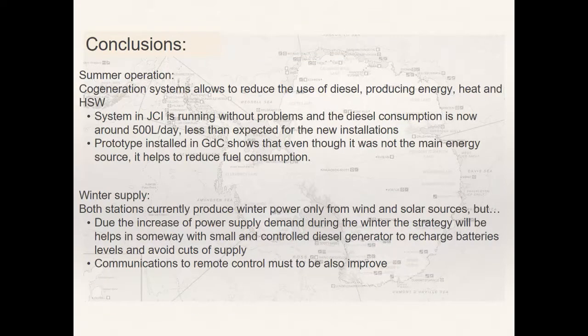Finally, we can summarize by saying that during the southern summer, the cogeneration system significantly reduced the use of fuel, producing the necessary heat and sanitary hot water for the stations. The system has been running successfully in Juan Carlos I during the last 3 seasons, with daily fuel consumption around 500 liters per day. This amount is significantly below what was estimated during the remodeling project.